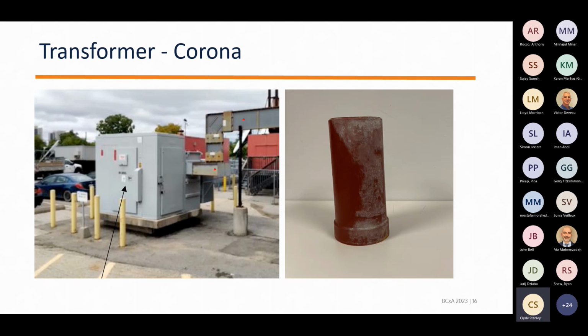Sometimes we do have one-year walkarounds after a project, and that should be in your spec. But here, this transformer started tracking and developed Corona. This is where ultrasonic testing is important, to make sure that transformer is in good health. Again, uptime is paramount.